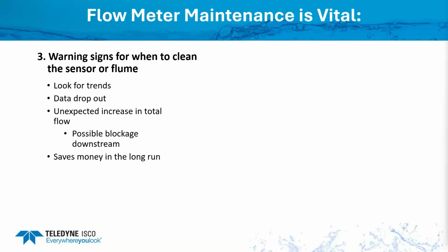So let's discuss some of the warning signs for when to clean your sensor or the flume. Again, look for trends. What we're looking for is a normal diurnal pattern during normal flows. It's going to change during the wet weather. You want to look for dropouts in the level, velocity, and signal strength. Other things to look for is an unexpected increase in total flow.